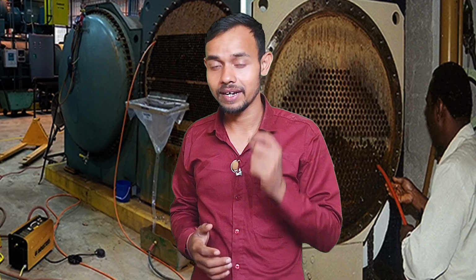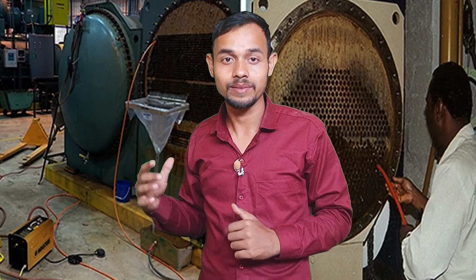Okay, friends, second is compressor overload. Yes, this is the most important thing. Scaling leads to hot return water, which leads to higher pressure, which leads to compressor trip. And the worst case is the compressor motor burns, massive repair cost. Okay, and next is energy consumption increase: after scaling there is a 15 to 30% energy consumption increase. The chiller is the largest energy consumer in HVAC. Yes, scaling means more power needed, and after removing scale there is power saving.